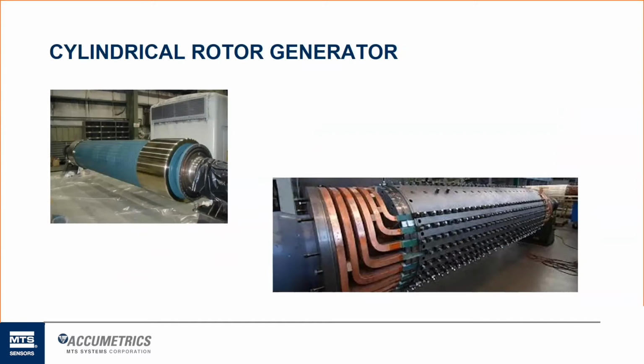Same concept. There's many thousands of these turns of wire. They're insulated from themselves with thin layers of insulation, and then they're also isolated from the metal of the rotor itself with fiberglass insulation pieces inside of these grooves. So the issue of a ground fault is you don't want there to be any current flow between the high voltage, high amperage flow of electricity in these bus bars and the metal of the machine itself, the forging of the rotor. If that happens, that can be very bad.